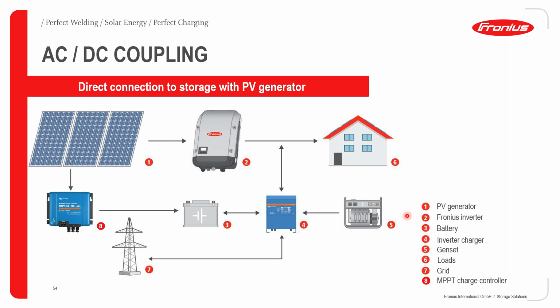So also the possibility to include a standby generator for maximum independence, especially if the grid is not available and you are in an off-grid kind of installation. You can have a small generator incorporated to ensure that your loads or your batteries never fully discharge to the point whereby the inverter charger from Victron is not able to restart.